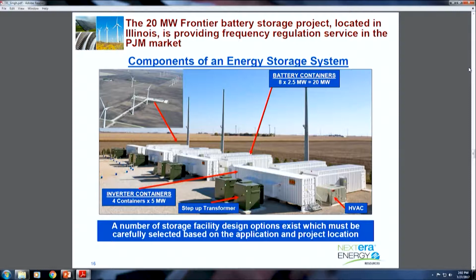One thing I want to point out is it's not just the battery alone, it's also the integration. What kind of battery do you pick for a different use case? Battery chemistries differ, so you have to be careful which chemistry gets picked, the type of inverter you pick, how you containerize batteries, whether they go in a container or a building, and what the permitting requirements are for the local jurisdiction. What are the fire suppression systems? When we go for permitting with local zoning authorities, we have to address all those issues, and how the different hardware and control systems talk with each other and to the grid. It's equally important, more than just the batteries.